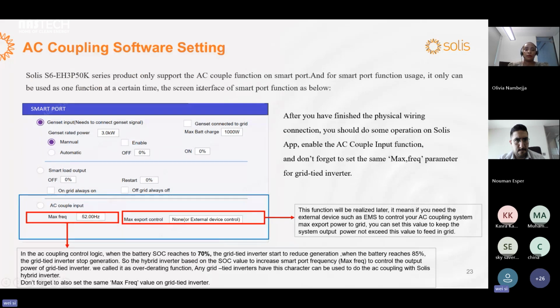Okay, about the setting. When you want to use the AC couple function, you should enable the smart port as the AC coupled input. Then you should set the max frequency, and the max export control. This function will be developed in the next month, so for these parameters, you just follow this explanation. When the SOC reaches 70%, the grid tied inverter starts to reduce the power generation. When the battery reaches 85%, the grid tied inverter stops generation. So it will not be harmful to the hybrid inverter with this working logic.